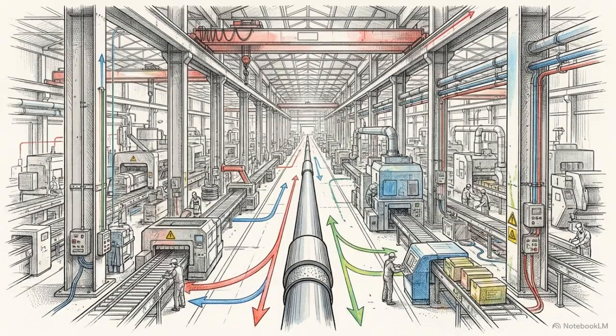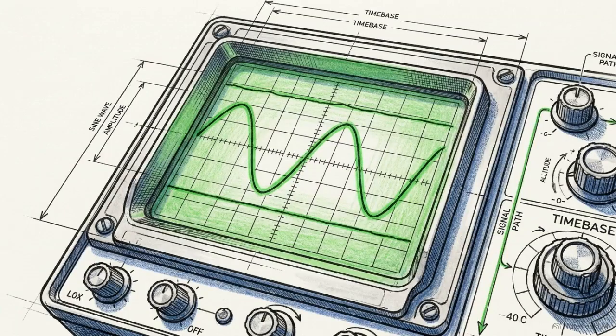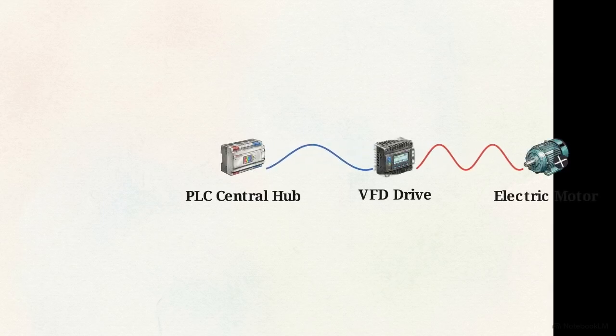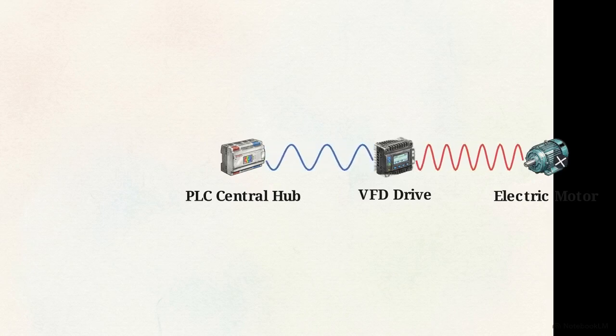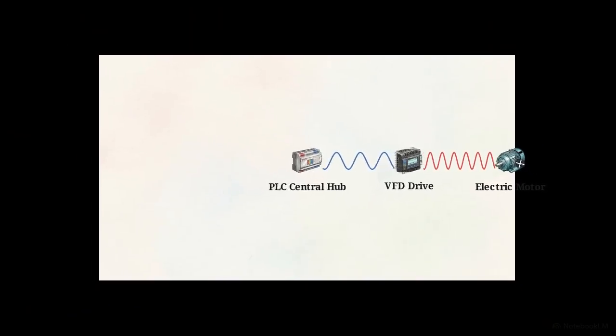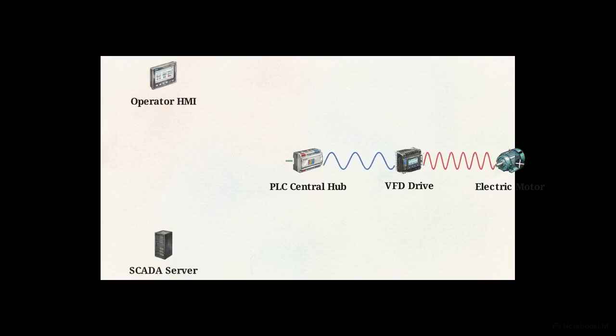By modulating current rather than voltage, analog signals can travel hundreds of feet across a noisy factory floor without suffering degradation from resistance or electromagnetic interference. A PLC can take that stable analog reading and output a precise command to a variable frequency drive, or VFD, continuously adjusting a motor's speed to match the live production requirements. This network topology maps how these local panels share their data factory-wide.